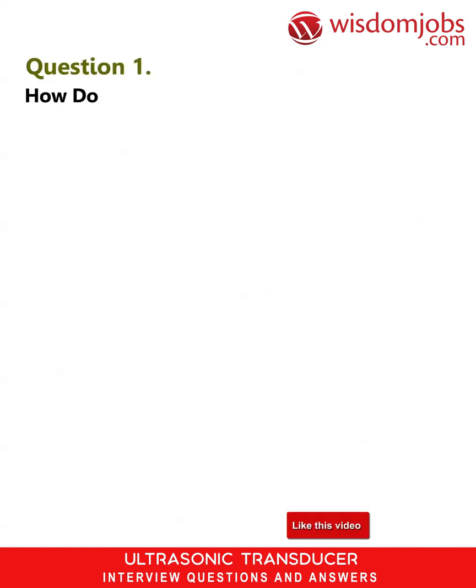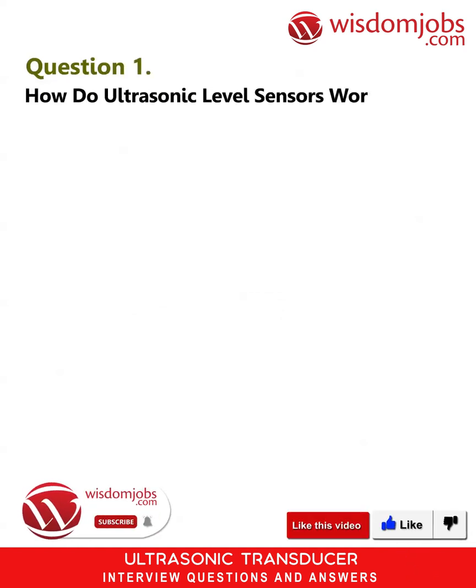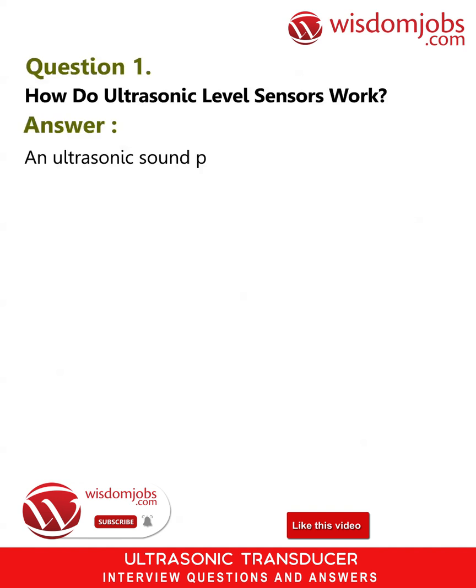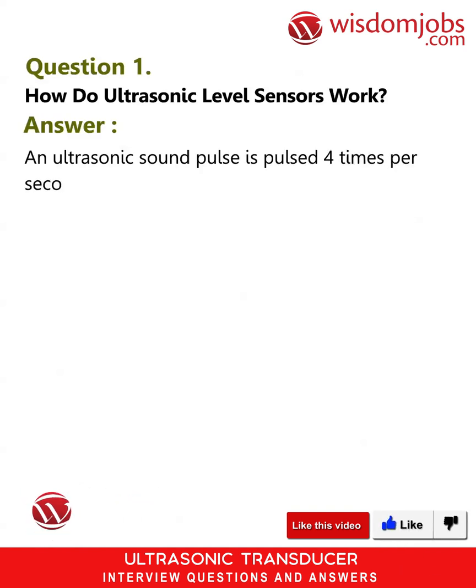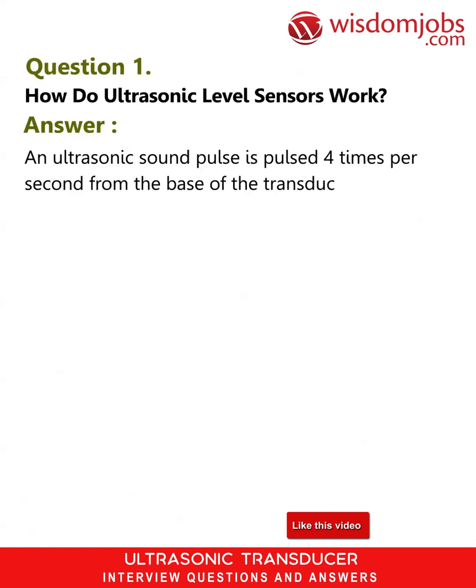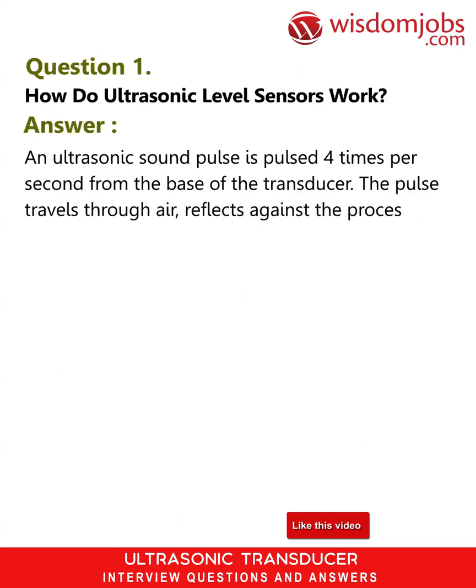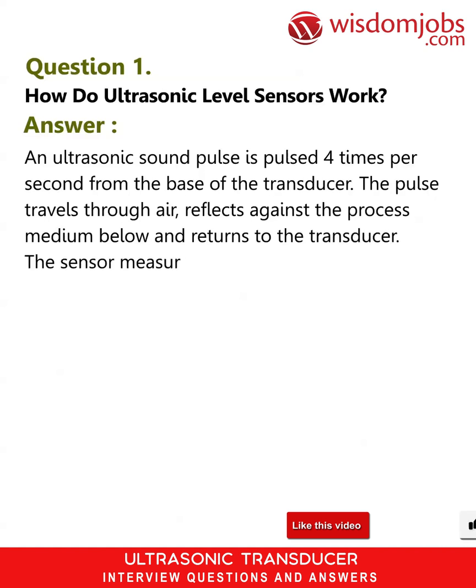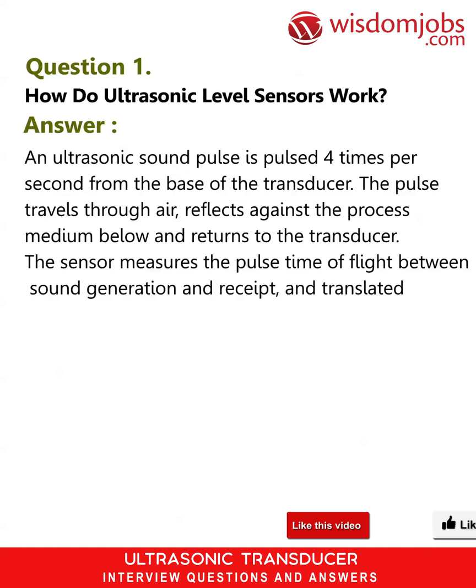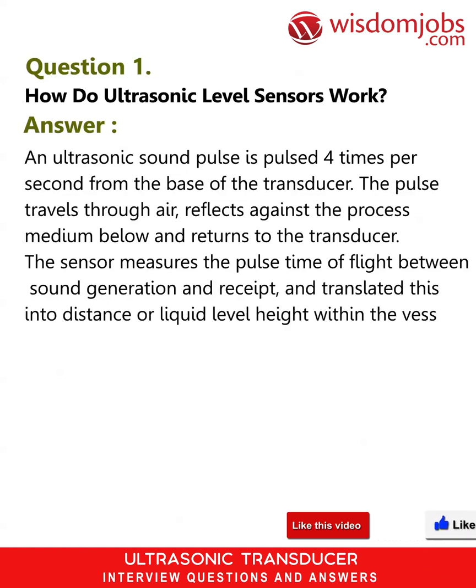Question 1. How do ultrasonic level sensors work? Answer. An ultrasonic sound pulse is pulsed 4 times per second from the base of the transducer. The pulse travels through air, reflects against the process medium below and returns to the transducer. The sensor measures the pulse time of flight between sound generation and receipt, and translates this into distance or liquid level height within the vessel.